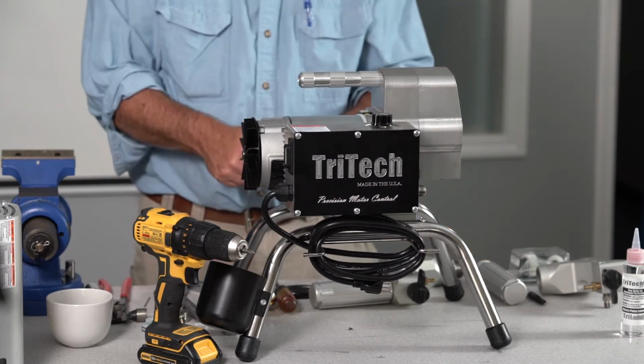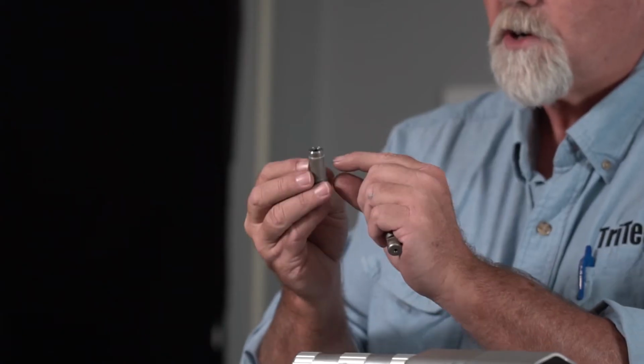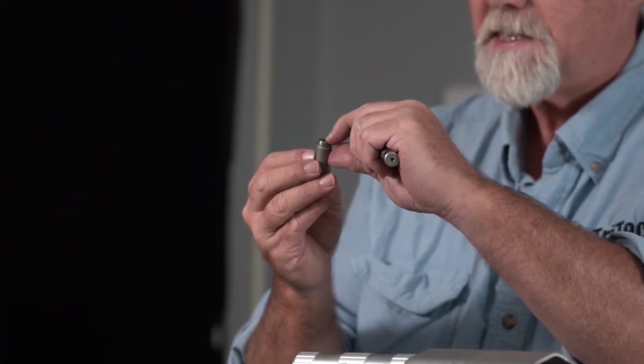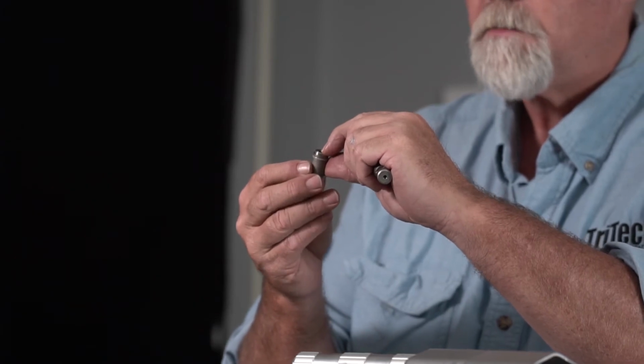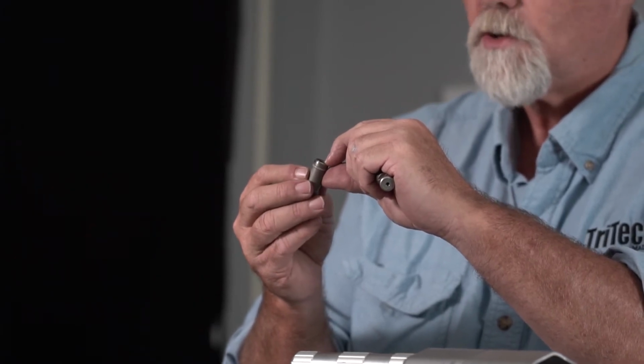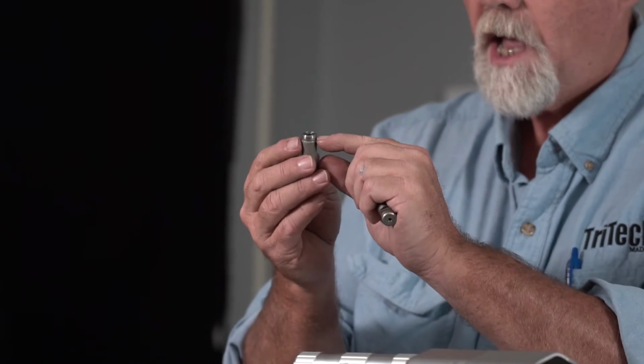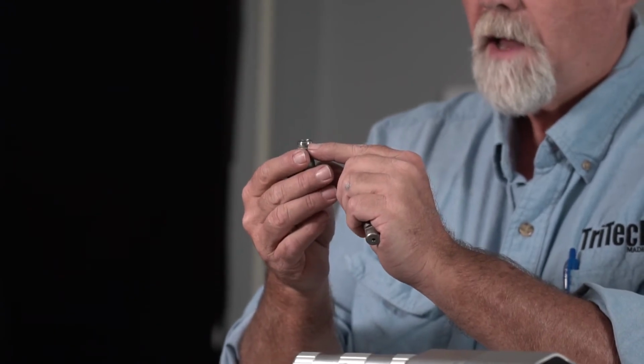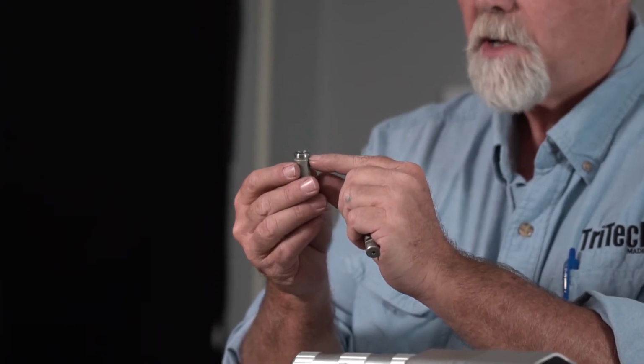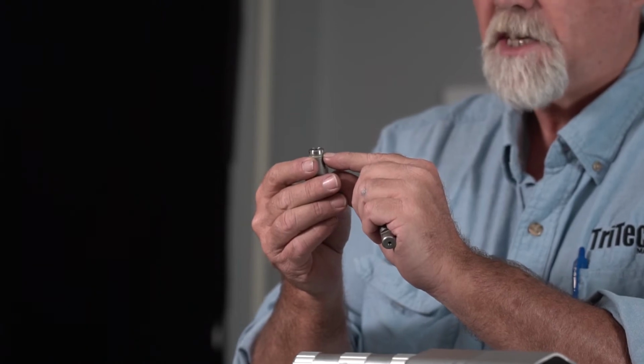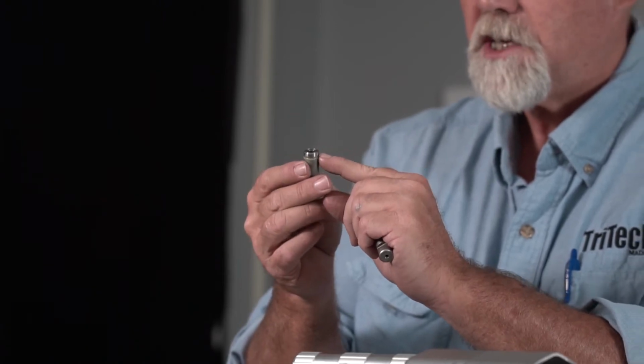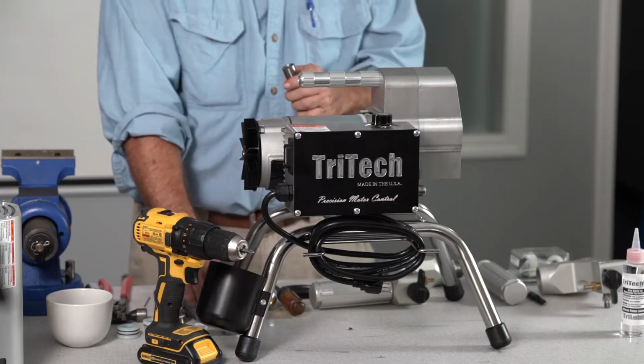Once you have the outlet valve housing out, you want to look at your outlet valve housing and look at the seat, the beveled edges, make sure there's no scratches or chips or imperfections, and you examine your O-ring for wear or damage. If it is, you can replace it. It's in the repair kit. If it's in good condition, it's okay to reuse it.